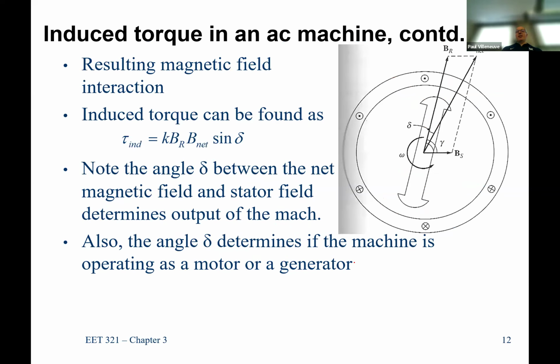Here's the concept of induced torque. Now we have two magnetic fields, one on the rotor and one on the stator. And the vector addition of those two becomes this net magnetic field. And they're always going to be approximately 30 to 40 degrees or less apart. You can certainly get something that's 90 degrees, but the problem with that is that you're at the limit of stability, and any change is going to cause you to become out of sync. You're actually going to slip a pole.